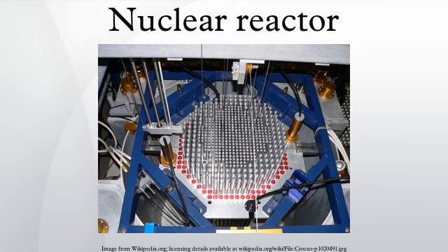Nuclear reactors generally have automatic and manual systems to scram the reactor in an emergency shutdown. These systems insert large amounts of poison into the reactor to shut the fission reaction down if unsafe conditions are detected or anticipated. Most types of reactors are sensitive to a process variously known as xenon poisoning, or the iodine pit. Xenon-135 produced in the fission process acts as a neutron poison that absorbs neutrons and therefore tends to shut the reactor down.